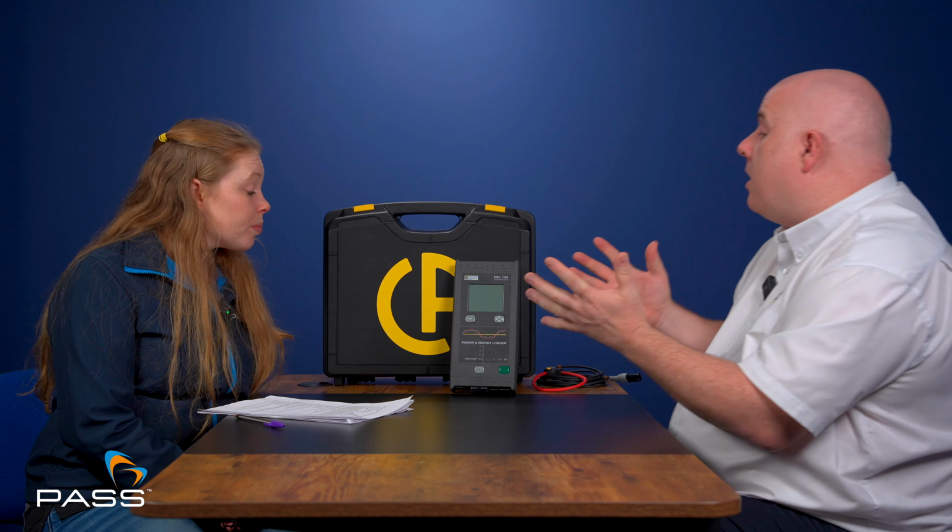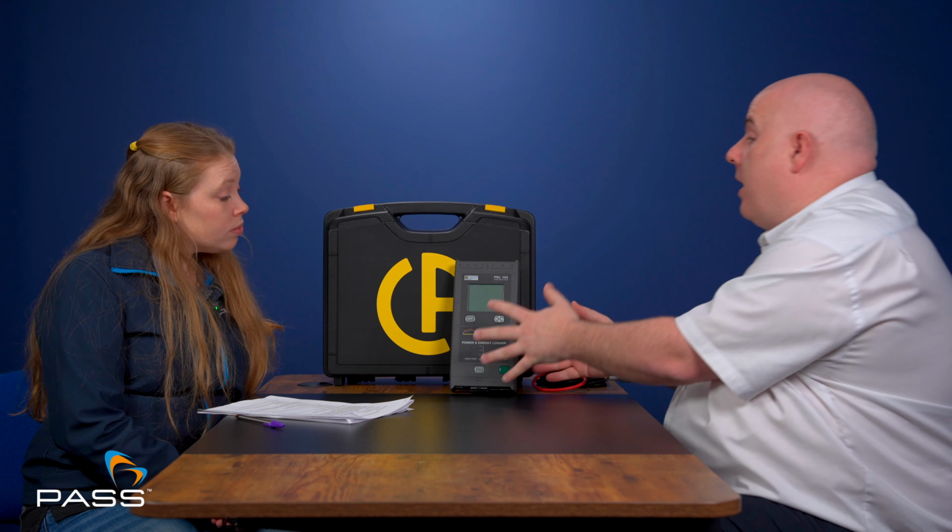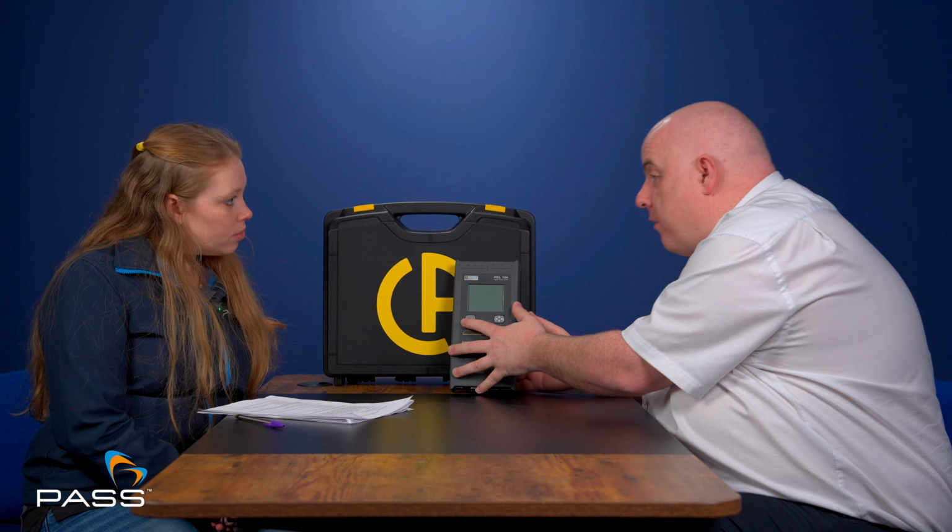Yeah, so the PEL 103 and the 104 from that regard are really what we would refer to as a three-phase power and energy logger. They're normally going to be used on three-phase electrical installations. However, they can be used on single-phase installations. Effectively, you've got three voltage inputs and three current inputs on there. So we can use those however we do. So like you say, split phase, if we've got two phases, three phases, single phase. They will also do DC installations as well. So that's something that people don't often realize.